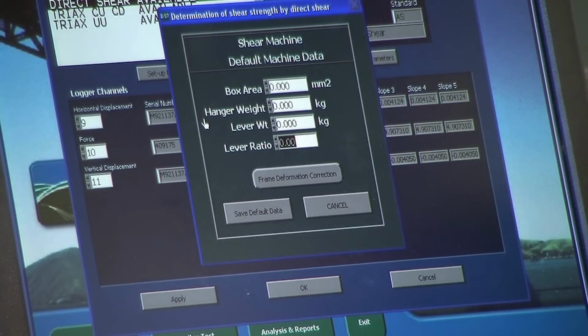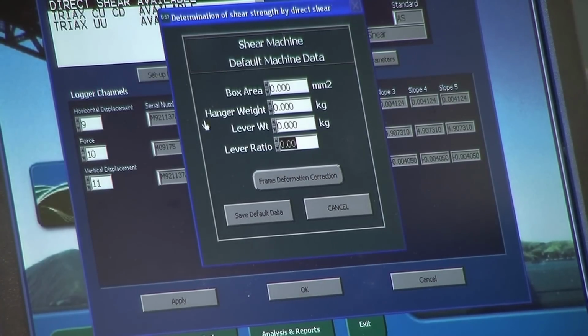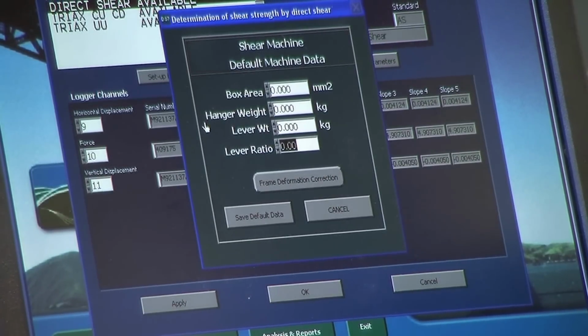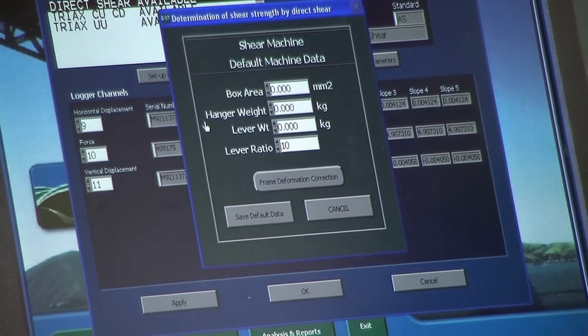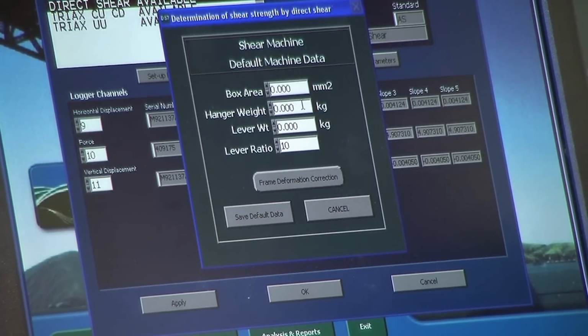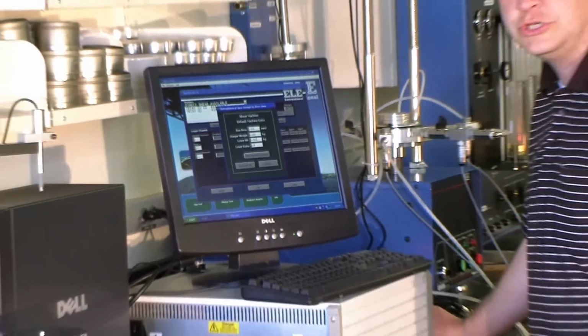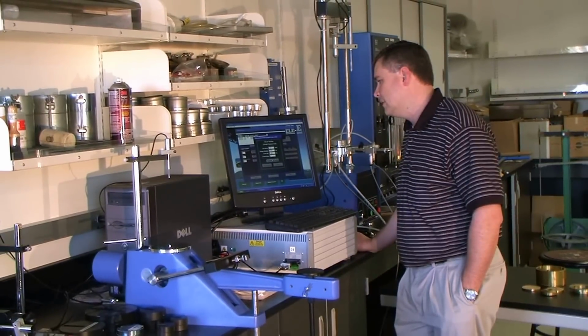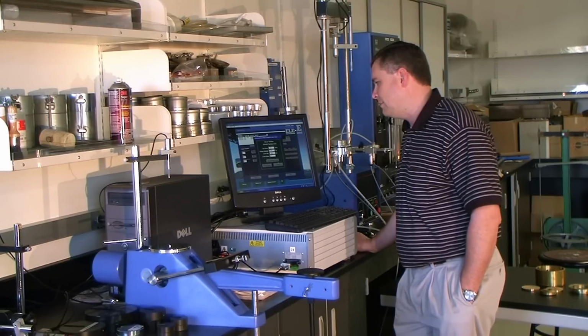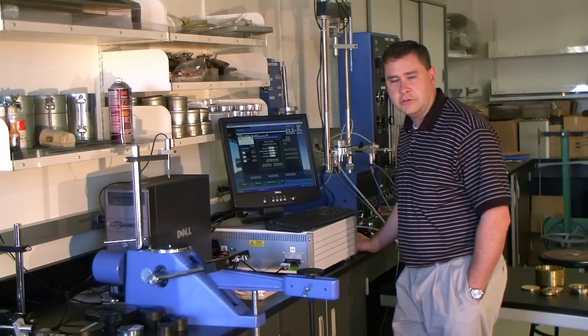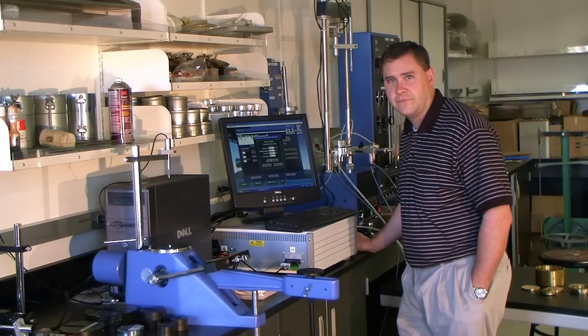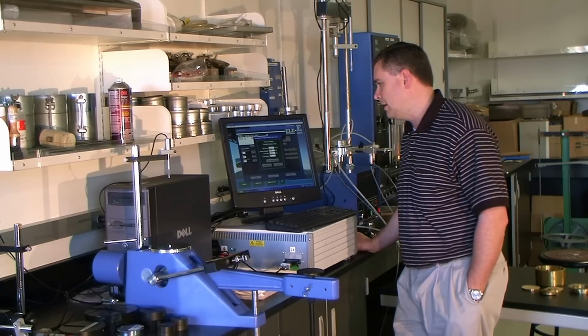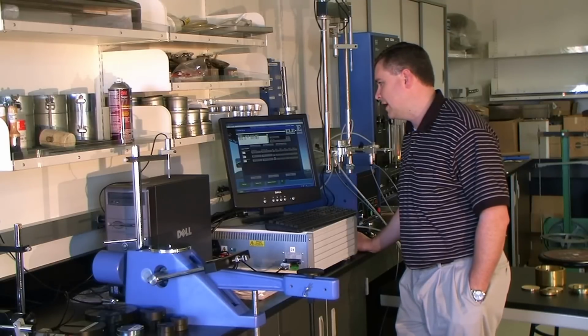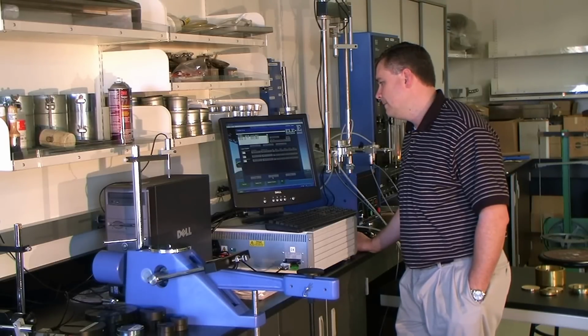But then you have a lever ratio. That lever ratio is going to be a 10 to 1 for this type of machine. It's all 10 to 1. We don't have a hanger or a lever weight. That's for more of a calibration if you have an issue with counterbalances. You can also, there's a frame deformation correction, which ASTM does have a section on that where you can correct the deformation of the frame based upon the weights that are applied. We won't go into that now. We'll just save default, hit apply, then click OK.